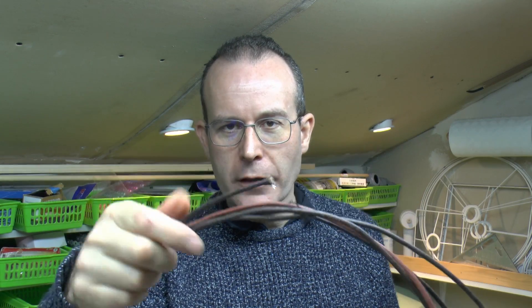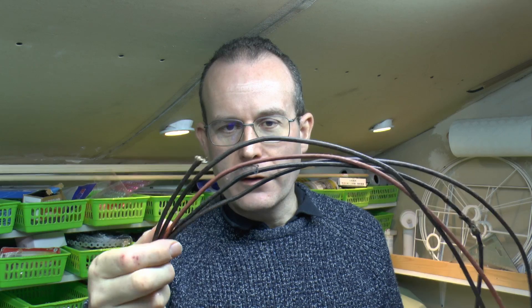Hello, I'm JW, and today we have some wires that were actually sent in. These are horribly old — rubber insulated with a cotton covering on the outside, in two colours: black and red. Of course, those were the colours used at the time. What we're going to do with these is heat them up to an excessive temperature by shoving far too much current through them, and see how they actually burn, and most importantly, how much smoke and toxic gases are given off.